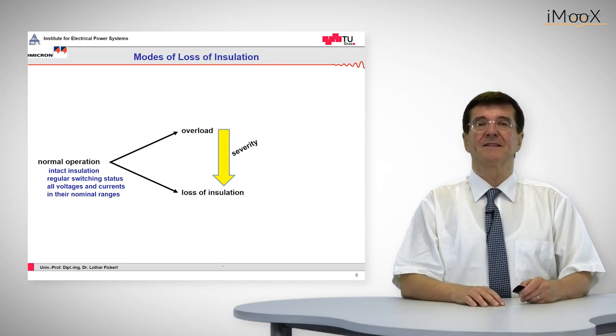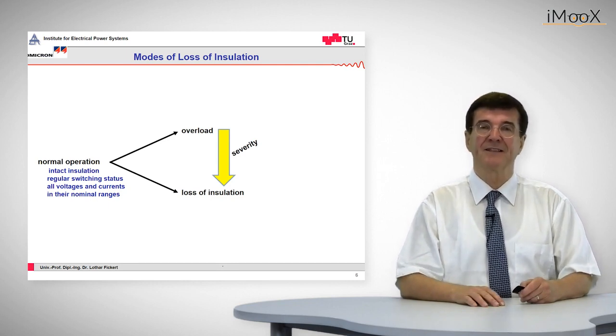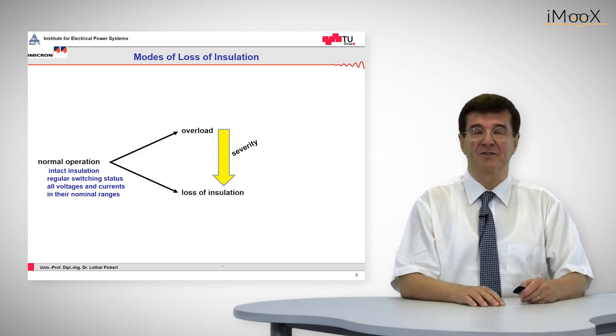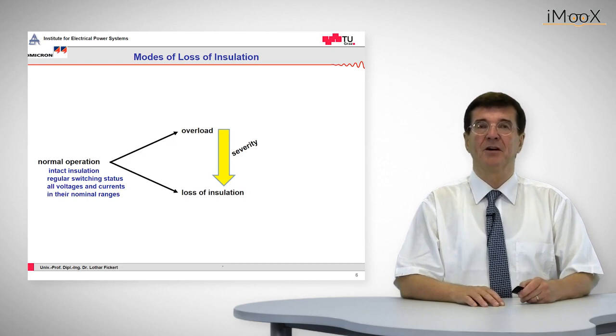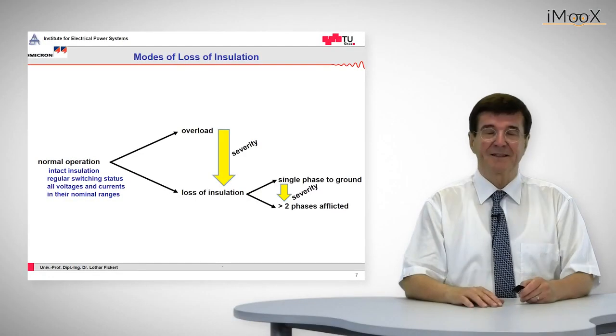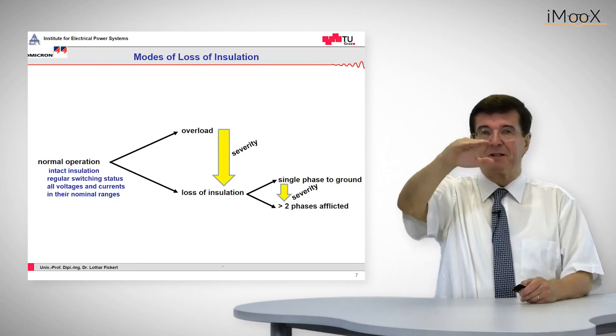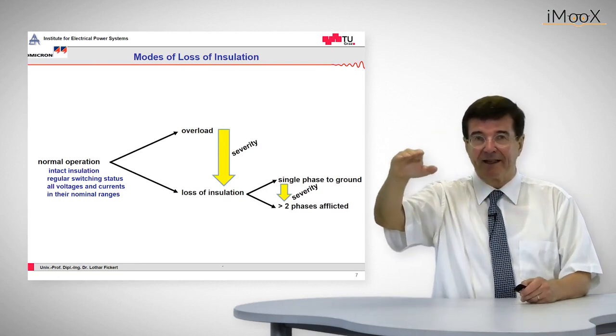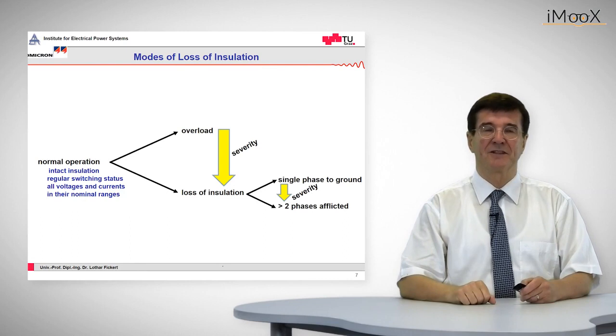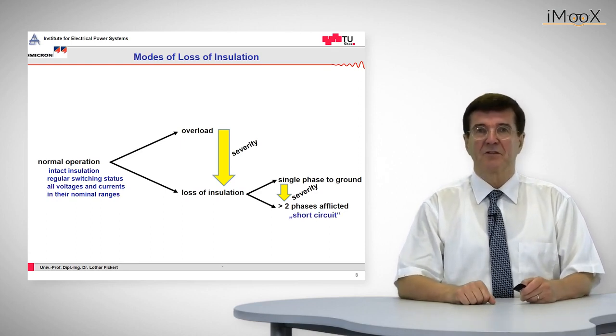So when these current-wise conditions are violated, then we speak either of overload or, in case of loss of insulation, of short circuits. Let's start with the overload. Overload means that the current goes slightly above the nominal current level and then is reduced, whereas in the loss of insulation we have either a single phase to ground fault or a multiple phase to ground fault, which are also called short circuits.